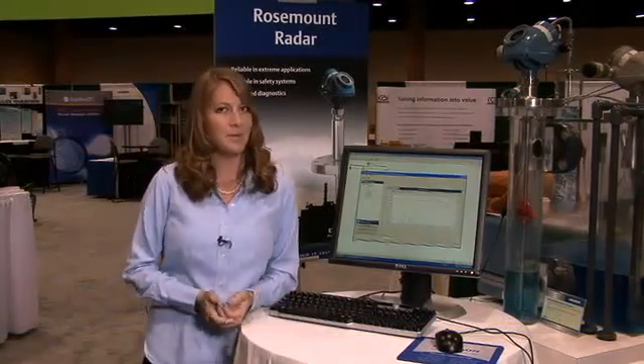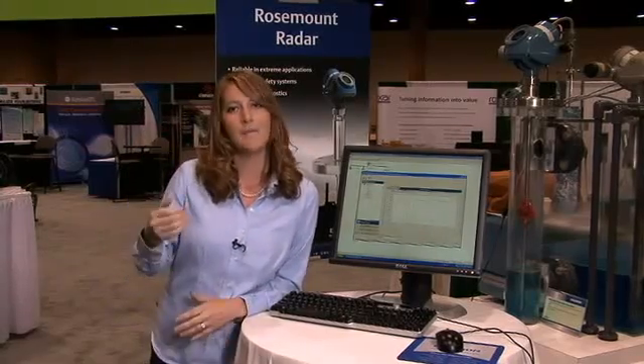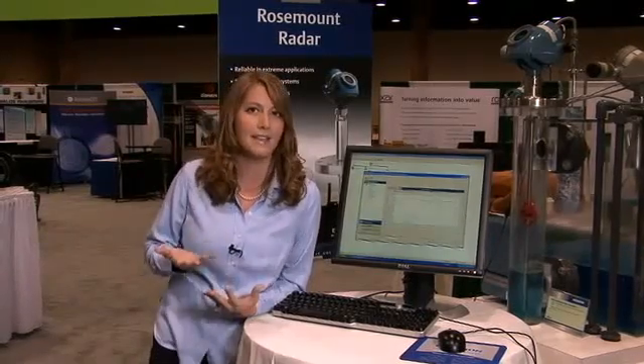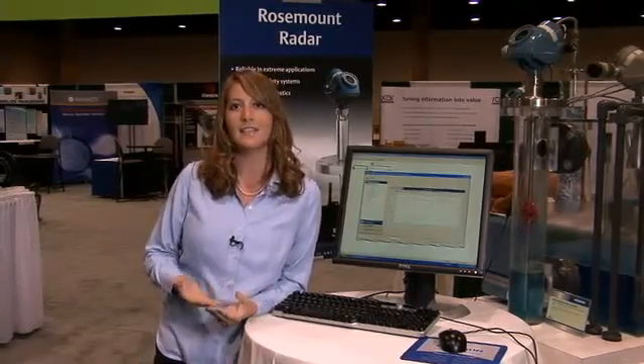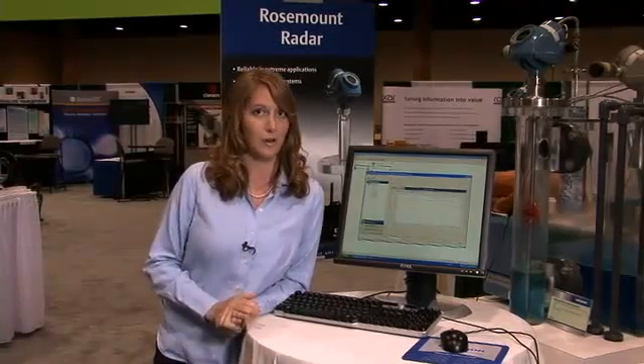The basic principle behind the Guided Wave Radar is that the electronics emit a high speed microwave signal and it's guided down the probe. When it reaches the surface it's reflected back into the transmitter and received as the level measurement. It looks like an echo pulse if you were to look at the echo curve.